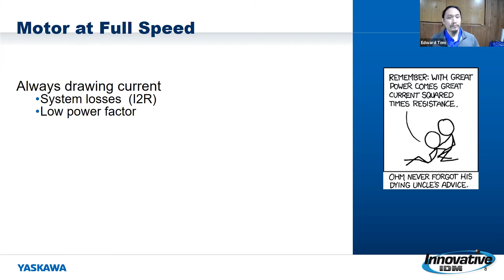The other thing is that if you are starting and stopping a machine for various reasons - say there was a small jam, you need to stop it and then restart it again - every time you start a motor up across the line, assuming you're not using any type of soft starter, you're going to see somewhere in the order of 6 to 8 times that motor's nameplate current show up. With that presence of current, you're going to have electrical stress on the system - the wiring that's out there, the motor, and anything connected in between. It is going to get stressed.